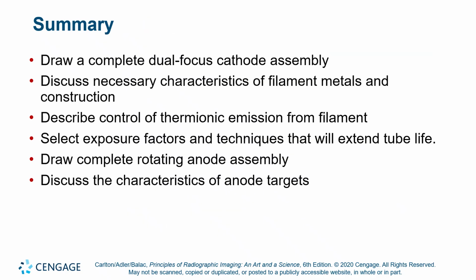All right. So that's the piece parts of our X-ray tube, our line focus principle, our anode heel, our bevel to our anode target. The reason that we have target rotation is for more heat capacity. The targets typically rotate somewhere between 3,000 RPM and 10 to 12,000 RPM. You're going to find 10,000, 12,000 RPM on your CT machines and in your fluoroscopy suites. Most of your conventional X-ray machines are going to be 3,000 RPMs. Your portable X-ray machines are going to be 3,000 RPMs.